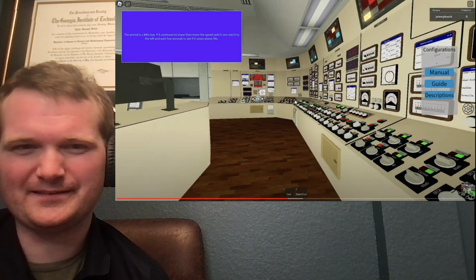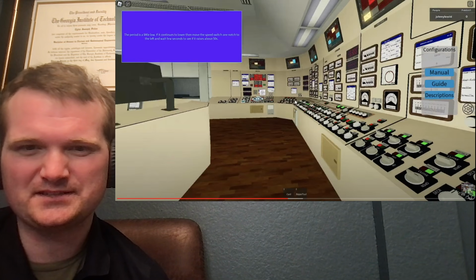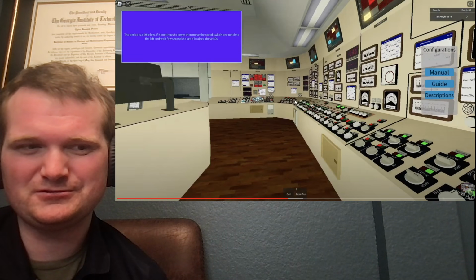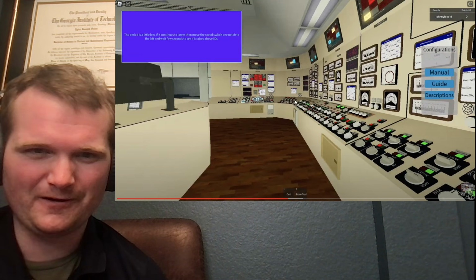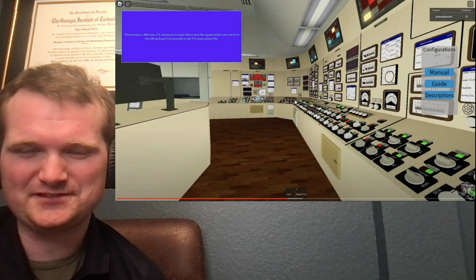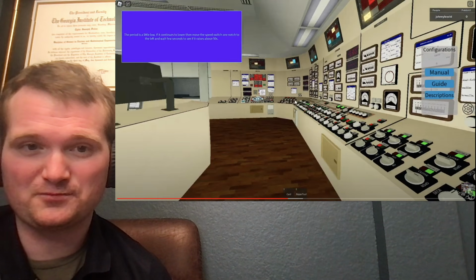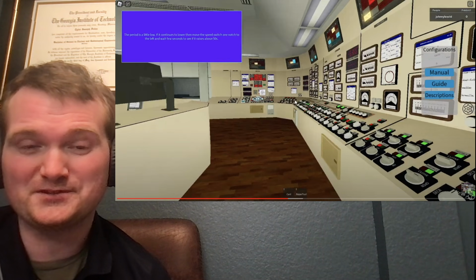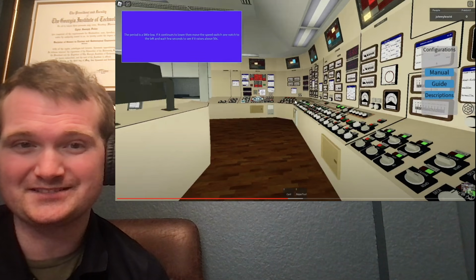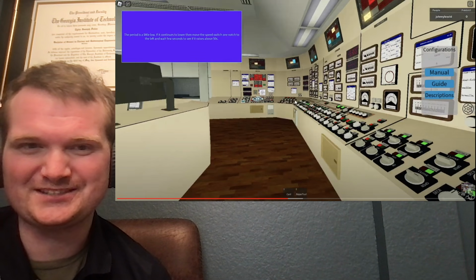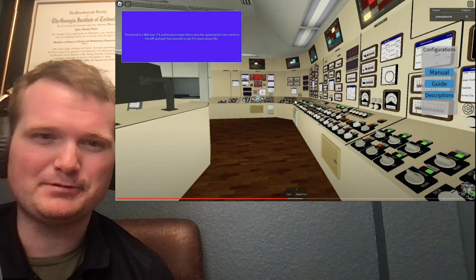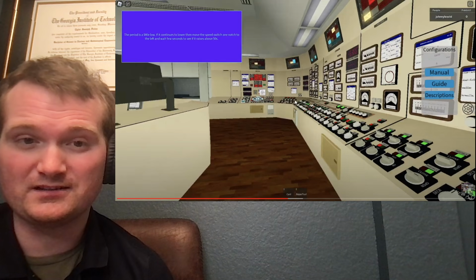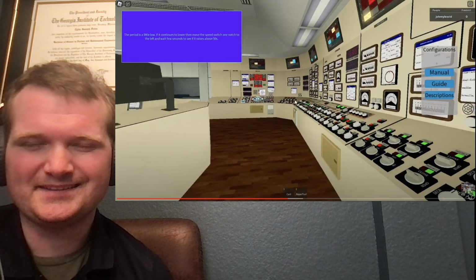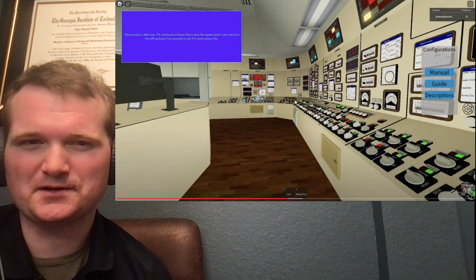that is one thing, and you'll see this as different compared to other industries. In some cases, you will do what's called a closed transition, where when doing electrical switching, you'll have something paralleled when switching power sources. Like if you were to swap, say, a bus from source 1 to source 2, you'll close both breakers and have both of them energize the same source, and then you'll open one of them. There's a time limit associated with that. It's typically about 30 seconds, but you will actually see that in nuclear, because in nuclear, you really don't want to lose power to something, compared to an open transition where you de-energize something to transfer from, say, source 1 to source 2. And that's a little different than electrical operations work in other industries.